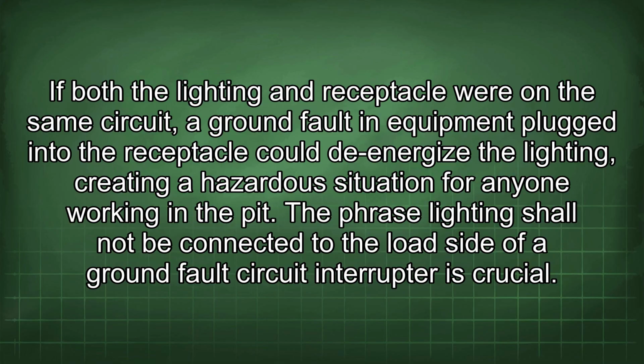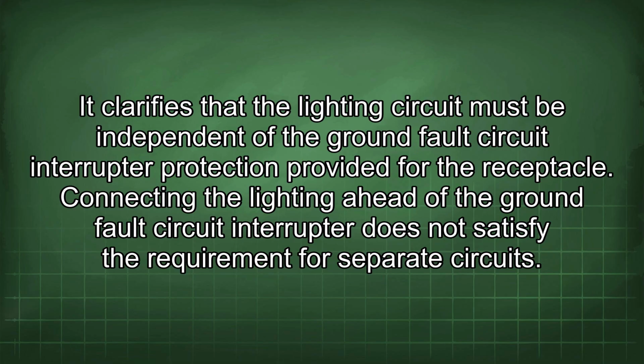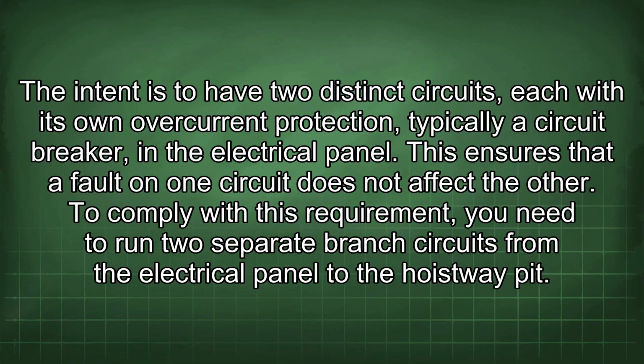The phrase "lighting shall not be connected to the load side of a ground fault circuit interrupter" is crucial. It clarifies that the lighting circuit must be independent of the ground fault circuit interrupter protection provided for the receptacle. Connecting the lighting ahead of the ground fault circuit interrupter does not satisfy the requirement for separate circuits. The intent is to have two distinct circuits, each with its own overcurrent protection, typically a circuit breaker, in the electrical panel. This ensures that a fault on one circuit does not affect the other.